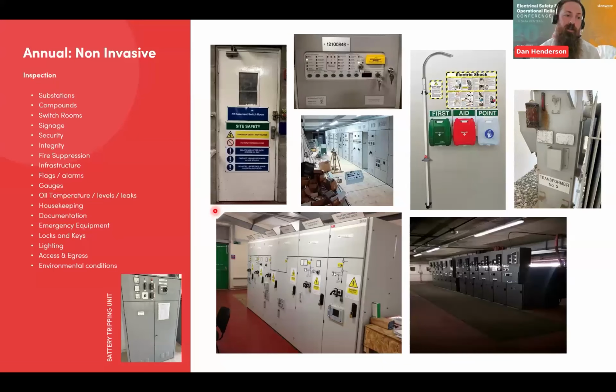Again, a bit of a caveat in there. But what we're going to be talking through is inspections of our substations, our transformer compounds, our switch compounds, the switch rooms, any of our electrical rooms and the equipment within there. It says 12 monthlies is obviously recommended. I think that's a little bit, it's horses for courses. It's down to the network. It's down to your site arrangements. But from my experience, 12 months would be too long.